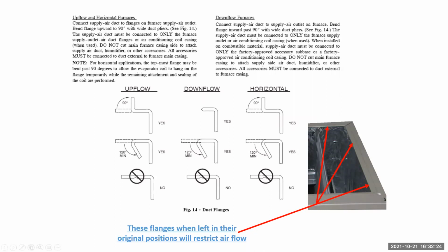If you're bending downwards, if you look under upflow, second picture down, it shows it being bent downwards 120 degrees minimum. That is a minimum. Get it bent as much as you possibly can, because you will get an air trap up in that little space between there, and it can create problems. At all costs, bend them as far as you can get them. And in no application does it allow those to stay flat. They're either up or bent all the way down in any application.